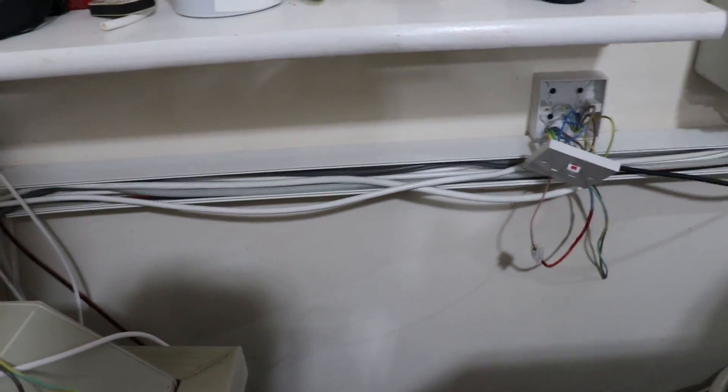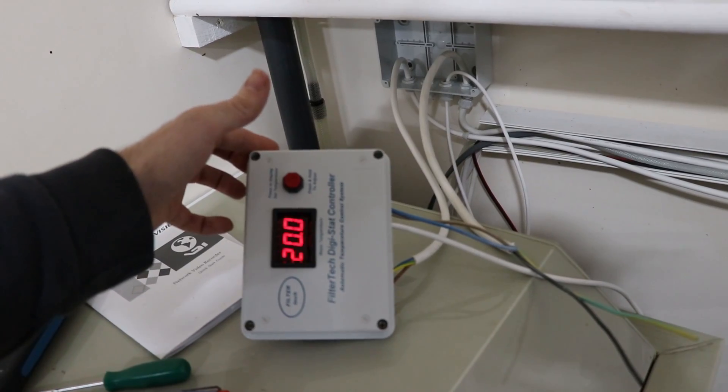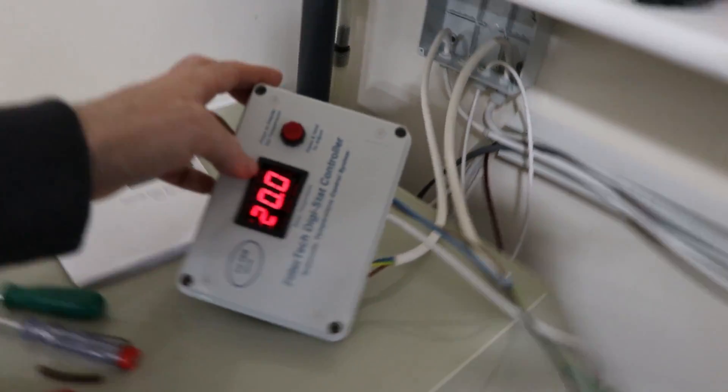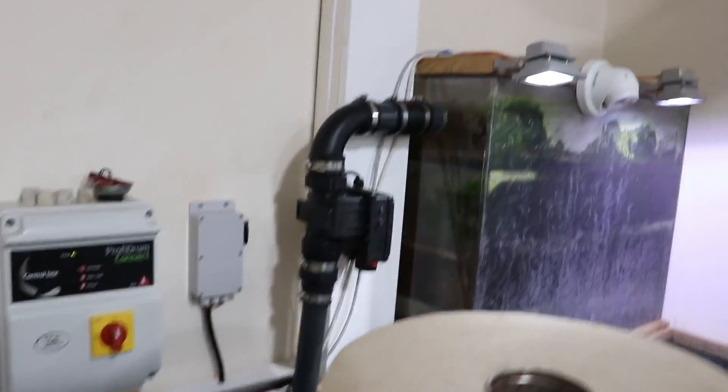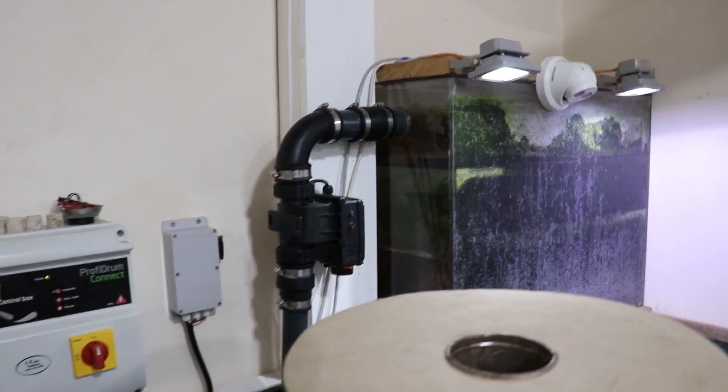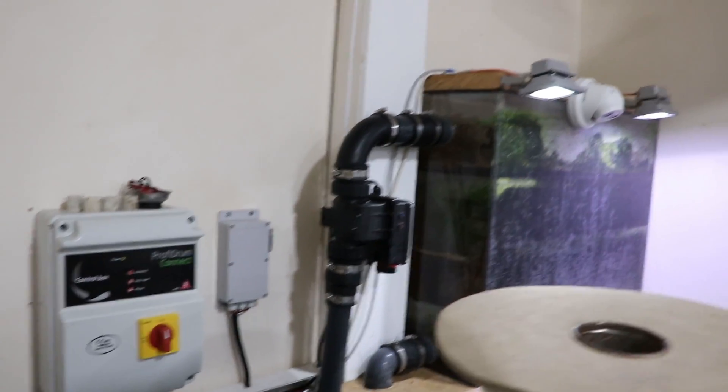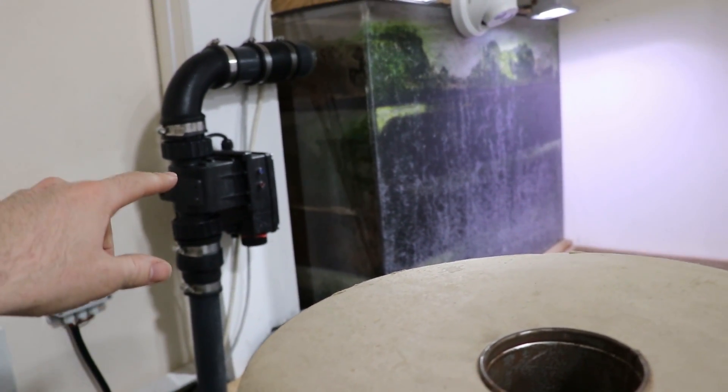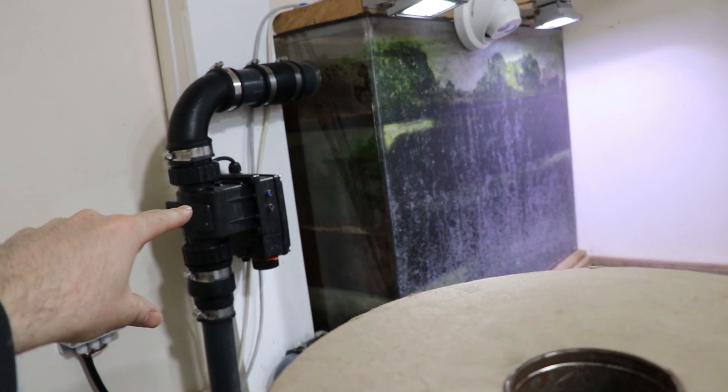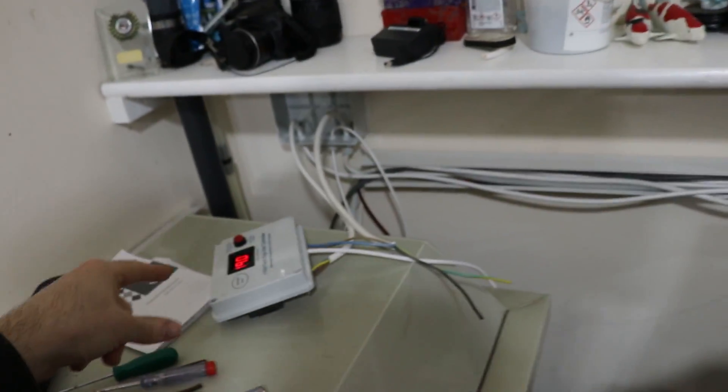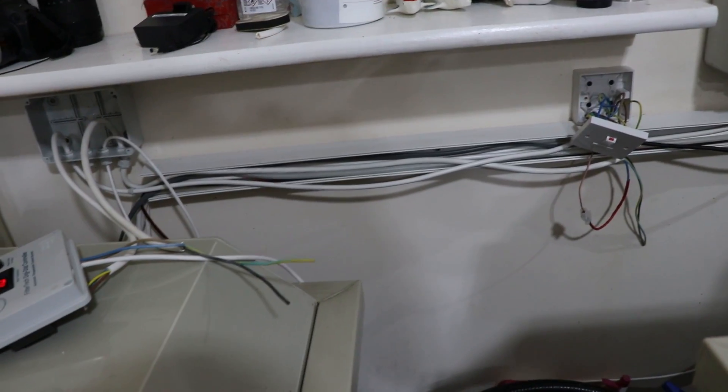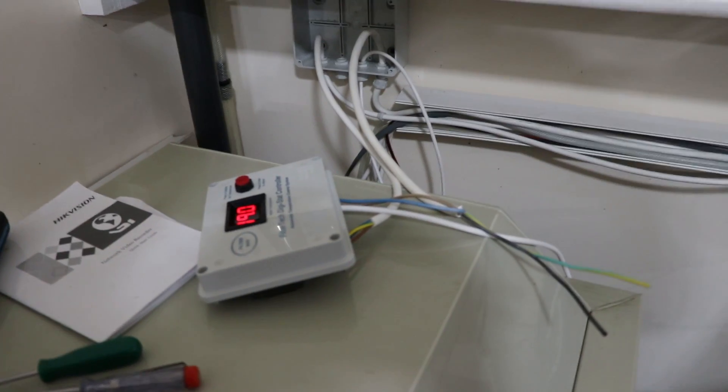However, I didn't want to wire it up like that, because that's a bit of a simple way of doing it. And it does work quite well. However, when, if I press that, so this is set to 20 degrees at the minute. And it's currently 19 degrees, that's just turned it off. As you can see, now it's turned it off. It's actually turned the entire system off, which works, but it's not how I wanted it. So what I want to do is bypass this thermostat, because that's also controlling it. And then the flow switch in this, I want to wire it to this, so that when there's not enough flow, this won't even try to ask that to turn on. And then I'll know it's working. It's unnecessary, but I can do it, so I'm going to.